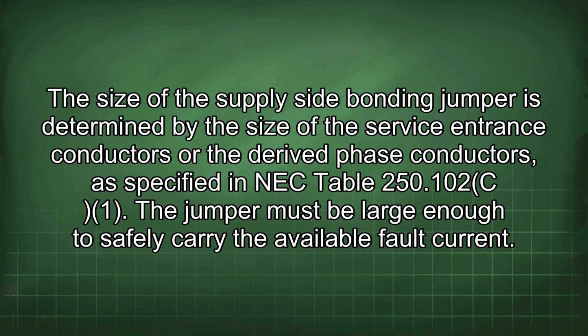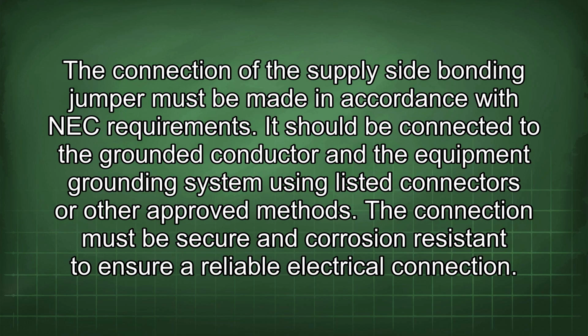The size of the supply-side bonding jumper is determined by the size of the service entrance conductors or the derived phase conductors, as specified in NEC Table 250.102. The jumper must be large enough to safely carry the available fault current. The connection of the supply-side bonding jumper must be made in accordance with NEC requirements. It should be connected to the grounded conductor and the equipment grounding system using listed connectors or other approved methods. The connection must be secure and corrosion resistant to ensure a reliable electrical connection.